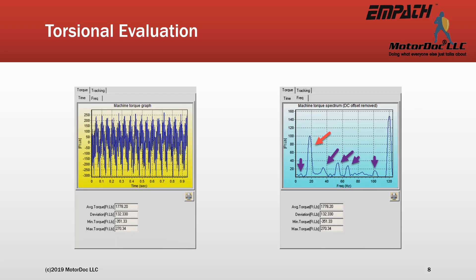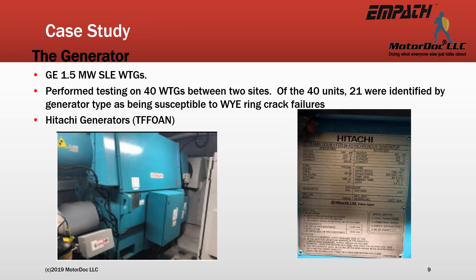These tools also allow a highly accurate analysis of other types of electric machines and their powertrains or loads. In this case study, we'll look at a common issue with the older GE wind generators, which is not unique to just this design or manufacturer. The EMPATH software was used with a data collector to look for cracked Y-ring connections in the rotor. 40 units were evaluated, with 21 being susceptible to this type of issue, of which 11 were found to have Y-ring fractures by testing.